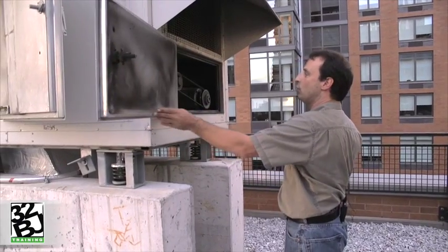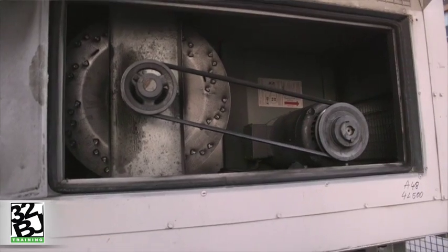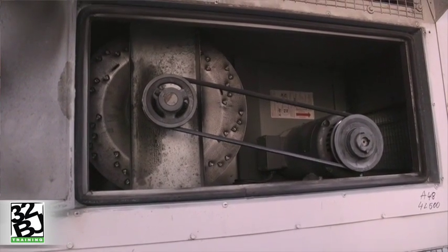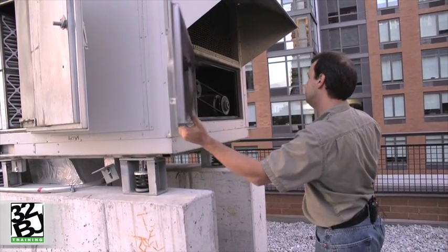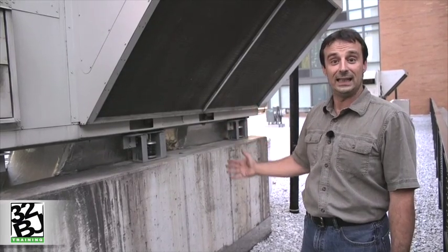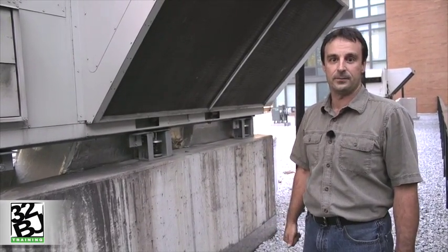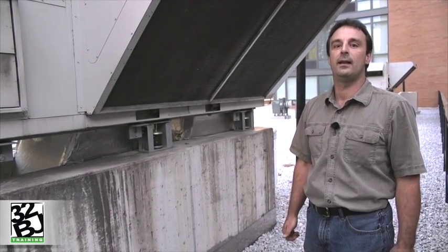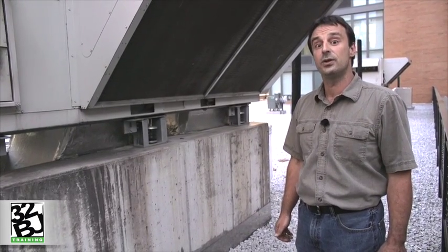Next, ensuring any belts inside your machine are properly tensioned and aligned and are in good shape. This is going to provide proper airflow to your common hallways. Ensuring that all coils are clean to increase heat transfer and reduce energy costs. And also, every 6 months, a good tightening of all line electrical connections inside the machine can significantly reduce motor failure.